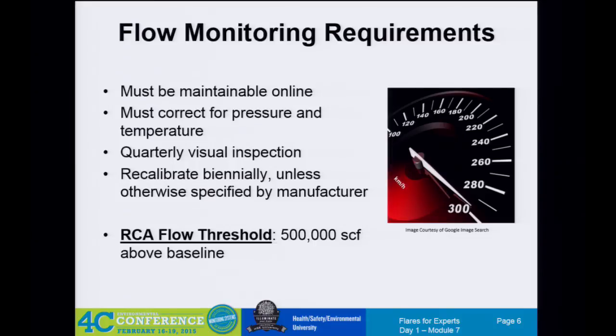And they put the transducers in there, measure the zero velocity, run a bunch of diagnostics. And as long as those diagnostic parameters are close enough to when they left the factory, then they say, okay, they put them back in the flare header, run some more diagnostics, again, close enough, you're good to go. There's no flow, they're not testing them against flow at any point. You still have these just radically screwy results from these ultrasonics.